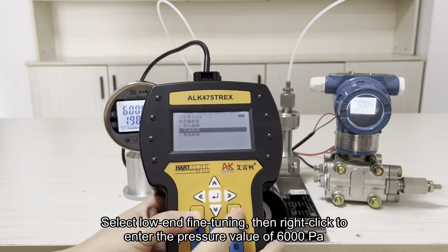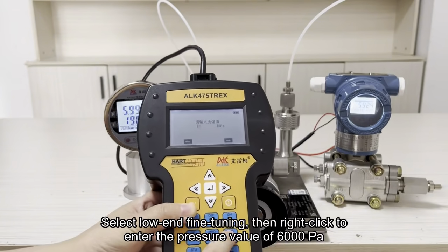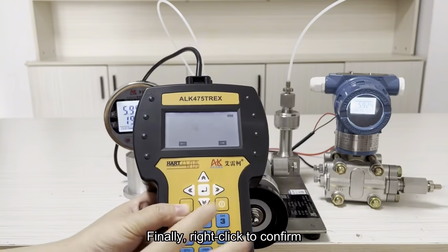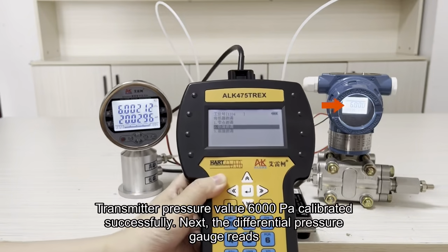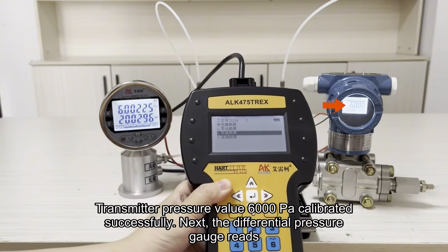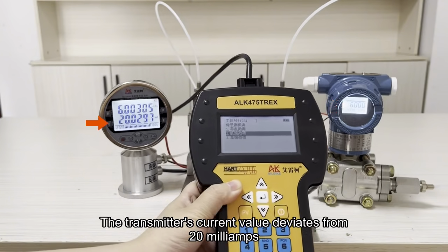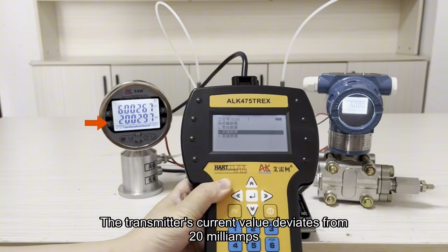Select low-end fine-tuning, then right-click to enter the pressure value of 6000 Pa. Finally, right-click to confirm. Transmitter pressure value 6000 Pa calibrated successfully. Next, the differential pressure gauge reads: the transmitter's current value deviates from 20 mA.